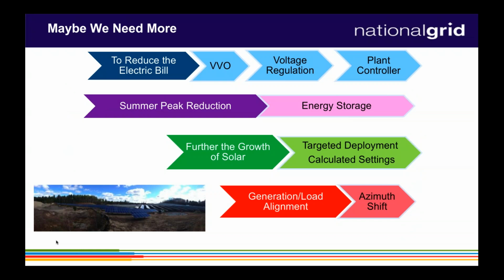Thinking about what we need to get there, and how we leverage different technologies and integrate them together—for example, we've been working with VVO, volt-var optimization, leveling the voltage across the feeder to reduce customer consumption and reduce the system peak. How do we tie that with advanced inverters to leverage data to control capacitors, or take information we have and use the advanced inverters to deliver VARs to better balance the voltage and reduce demand? That's an area where we're trying to figure out that linkage between volt-var optimization and advanced inverters.